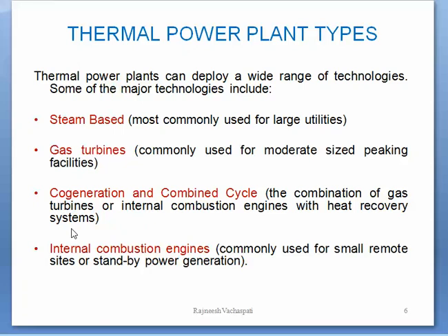A combined cycle power plant uses both a gas and a steam turbine together to produce up to 50% more electricity from the same fuel than a traditional simple cycle plant. The waste heat from the gas turbine is routed to the nearby waste heat recovery boiler to generate steam, and operate a steam turbine which generates extra power.